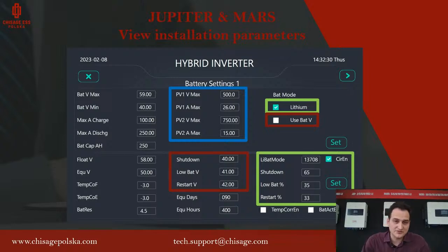In the middle, the blue frame, we have the PV information: PV voltage maximum and PV current maximum. Make sure that the PV voltage maximum is the real maximum voltage of our PV installation. So if the maximum voltage is 400, put 400. If it's 700, put 700. If we have 250, don't leave the 700 as default. Just make sure this information is correct.